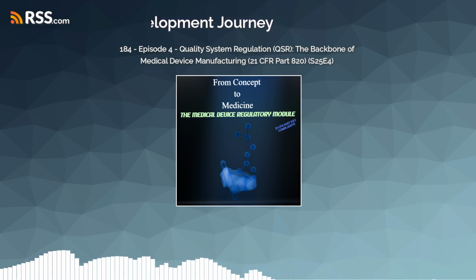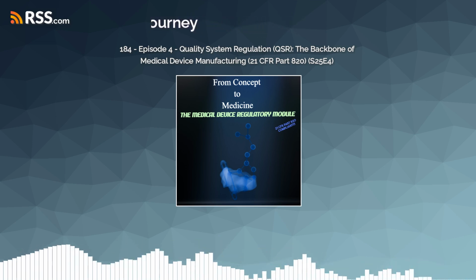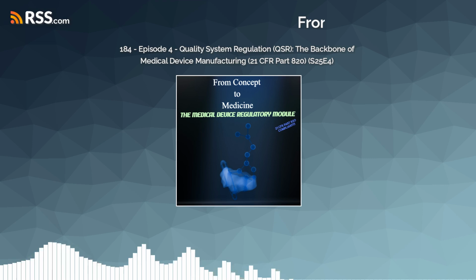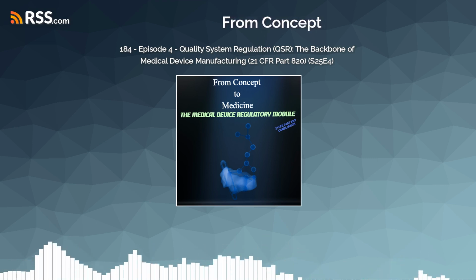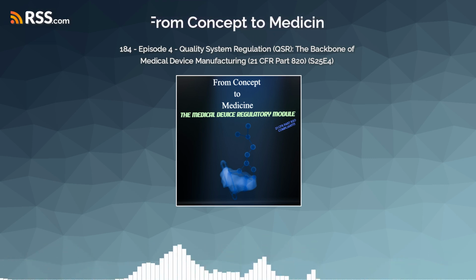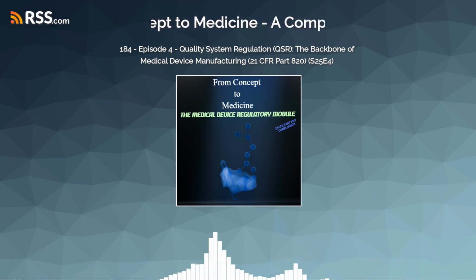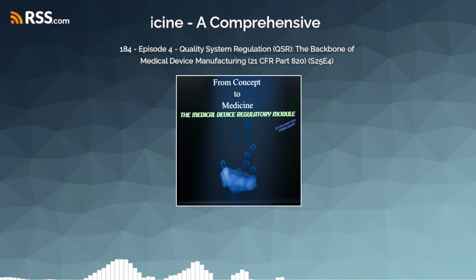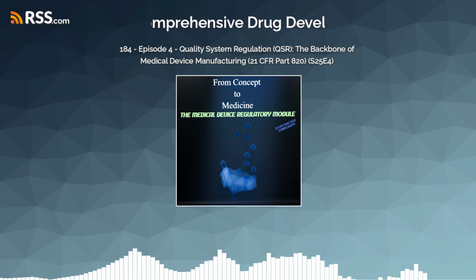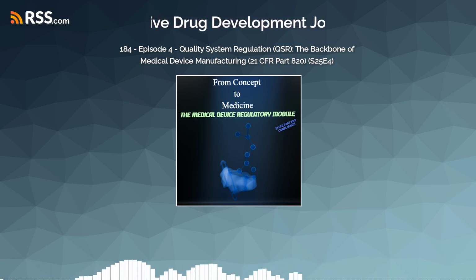Everything's in there. Design inputs, what does it need to do? Design outputs, what did we actually design? All the reviews, the testing, verification, validation activities. It's the proof. Okay, so the DHF is the story. Then how do you prove the device was designed right? You mentioned verification. How does that work practically? And how is it different from validation?